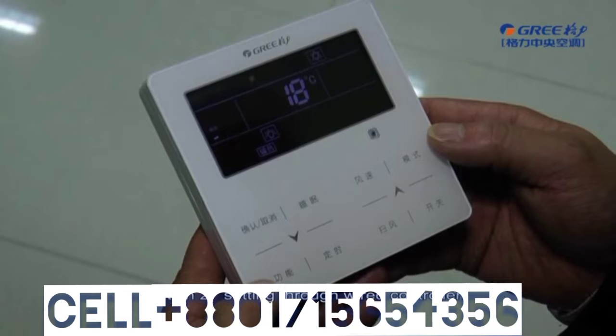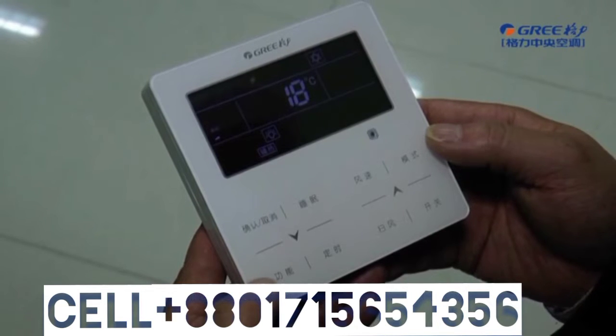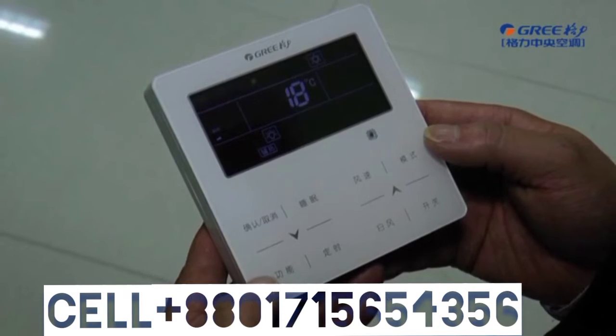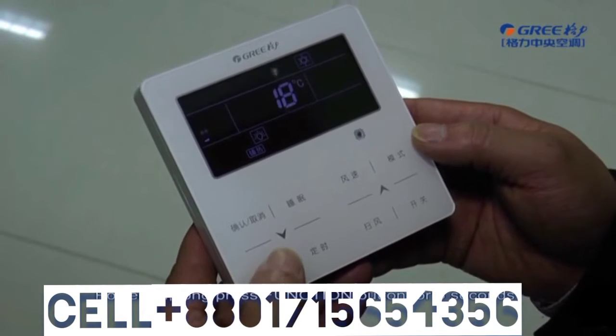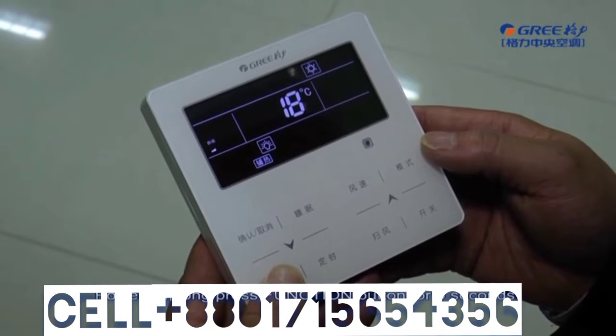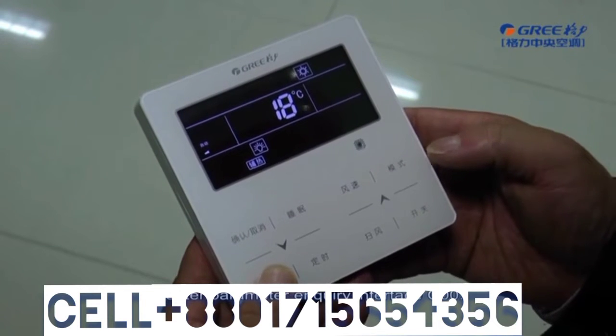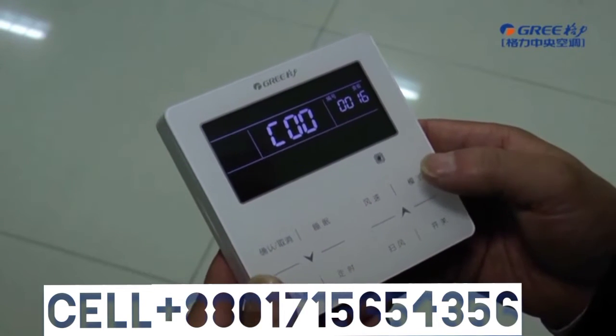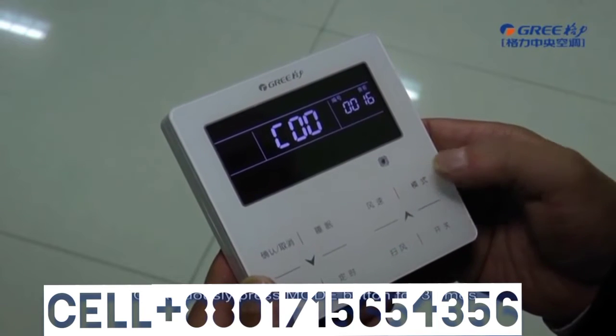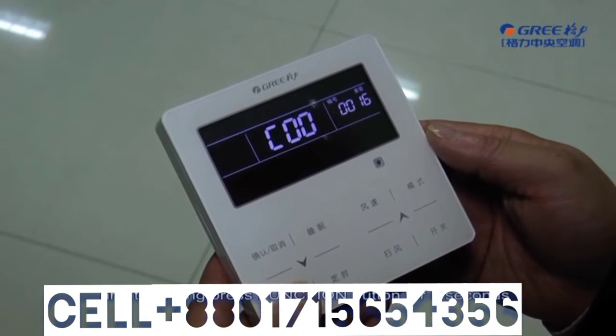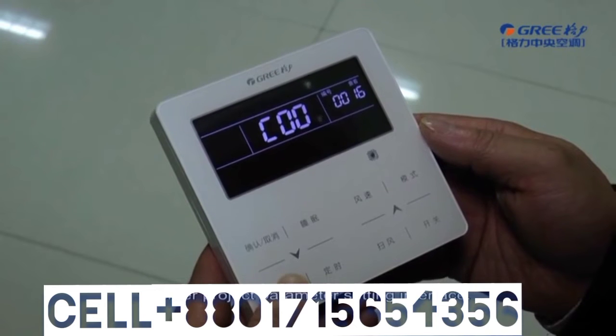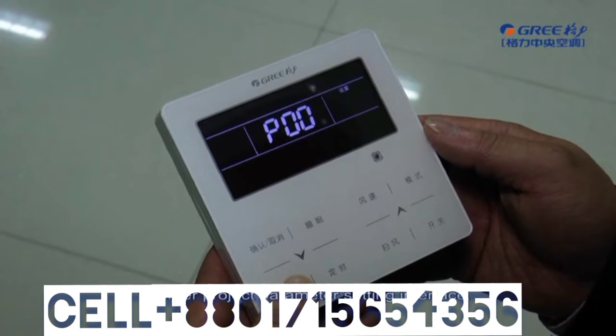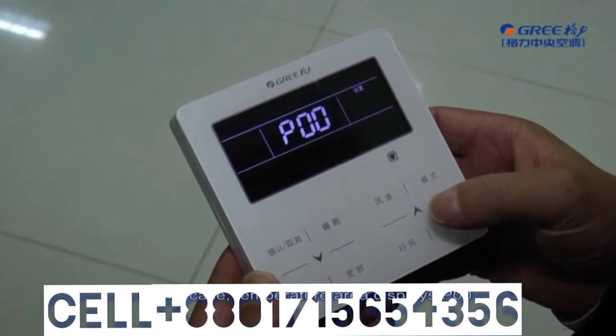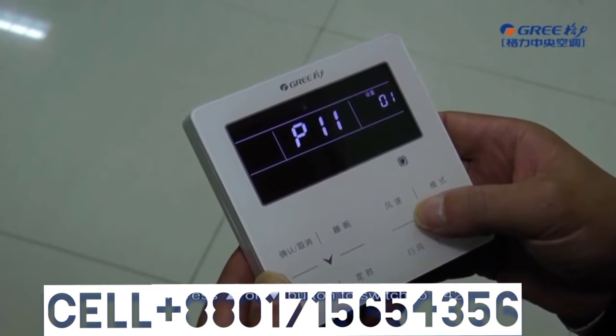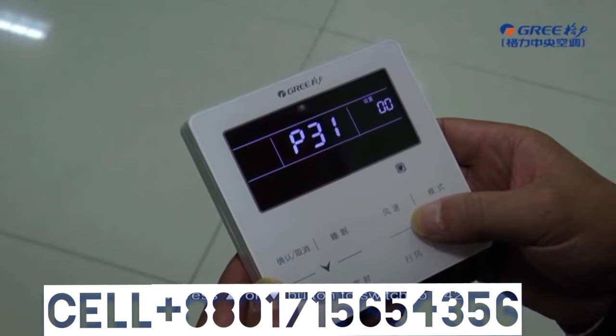Option 2. Setting through wired controller. Operation procedures. Power on. Long press function button for 5 seconds to enter parameter inquiry interface, C00. Continuously press mode button for 3 times and then long press function button for 5 seconds to enter project parameter setting interface. In this case, temperature area displays P00 and press up or down button to switch to P42.